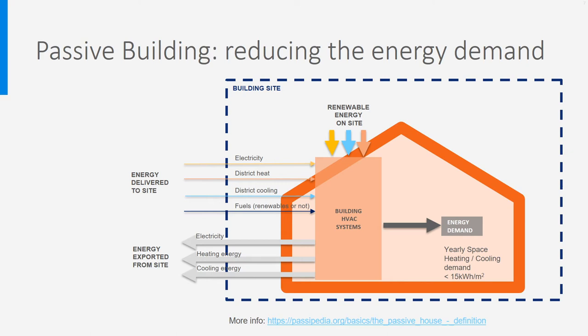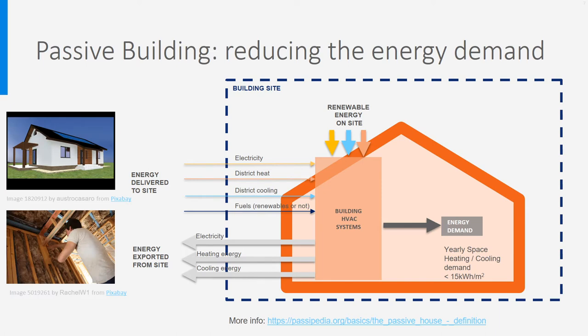To achieve this, a high level of insulation is needed, high efficiency glazing should be used, and a ventilation system should apply heat recovery. Such a house should be able to create good indoor comfort with almost no heating or cooling system — the heat produced by appliances like laptops and lighting, and the heat from human activity, should be enough to heat the house. From the cooling point of view, the house should be designed so that no cooling system is needed; using cold night air or air cooled in pipes in the ground should suffice.